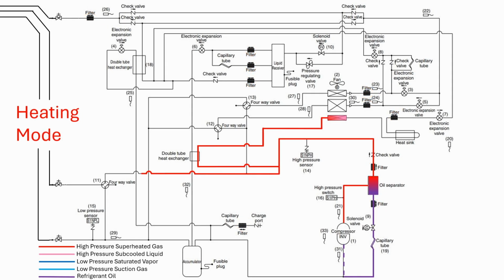As the refrigerant passes through the outdoor heat exchanger, it is subcooled into a liquid. The smallest section of this heat exchanger, which is the bottom in this case, first passes through a heat sink to cool the inverter section of the control board. After the subcooled liquid refrigerant leaves the heat sink, it passes through an electronic expansion valve, which in this case is pulsed wide open so it is not metering. The refrigerant then travels to a spot where it meets up with the liquid refrigerant coming back from the indoor units.